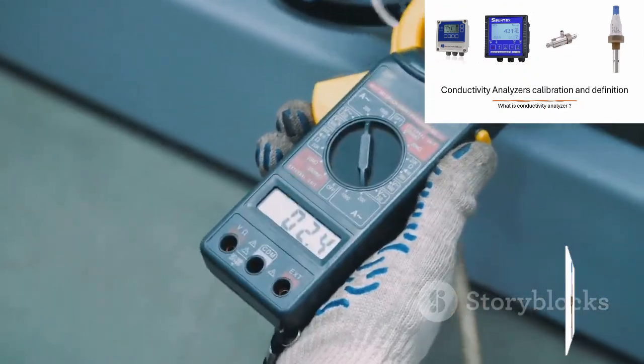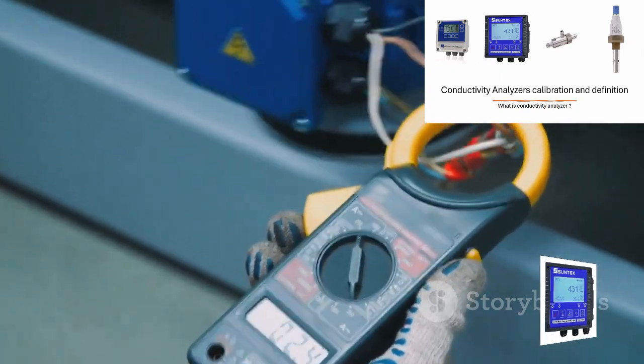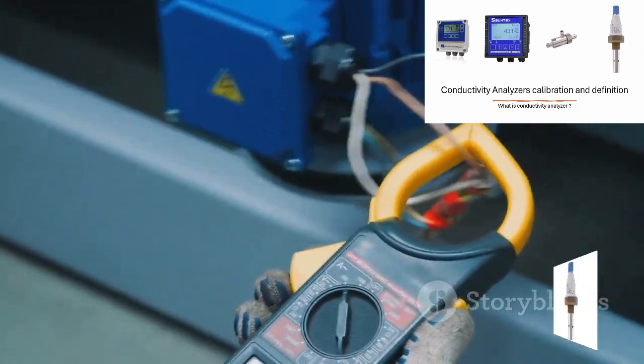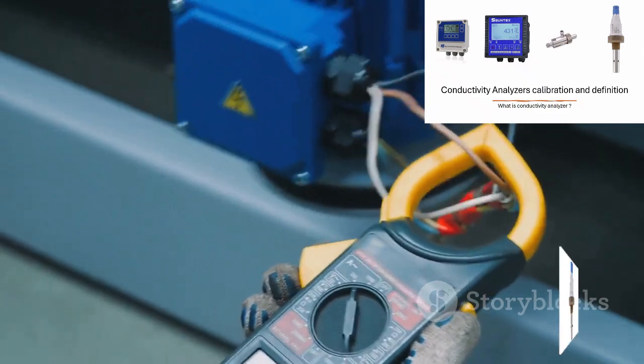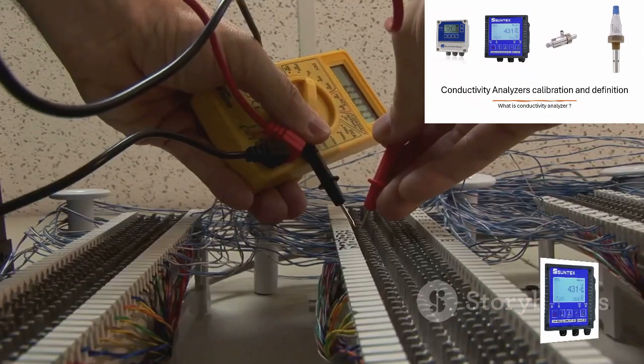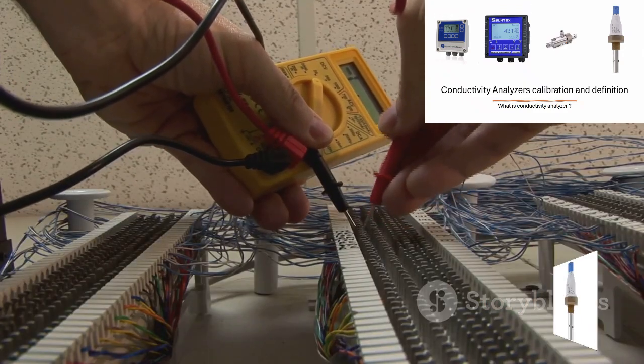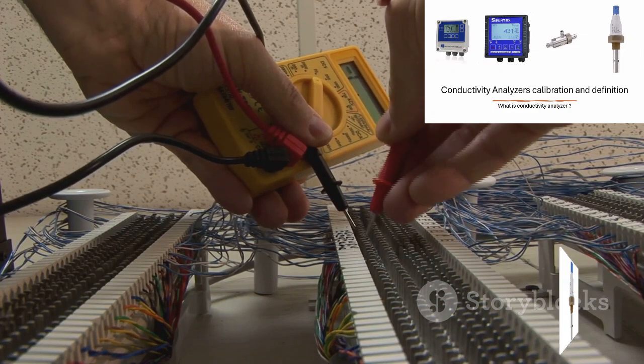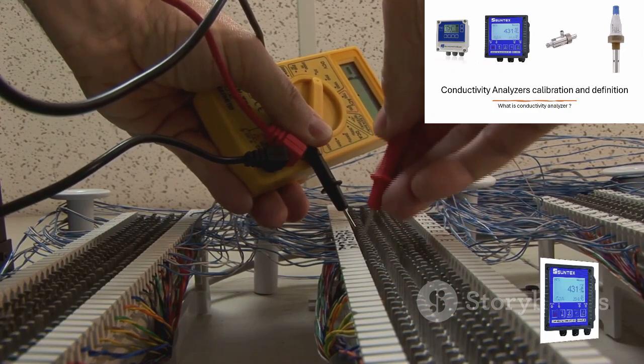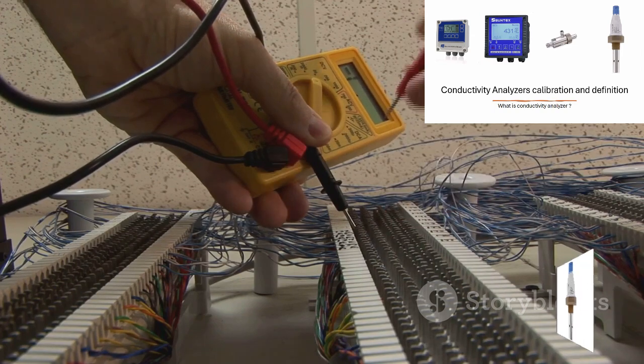Next up, you'll need your meter. The meter is the brain of the operation. It's the device the sensor plugs into. It has a screen that displays the conductivity reading, usually in units like microsiemens per centimeter or millisiemens per centimeter. This is where you'll see the numbers and make the adjustments during calibration.